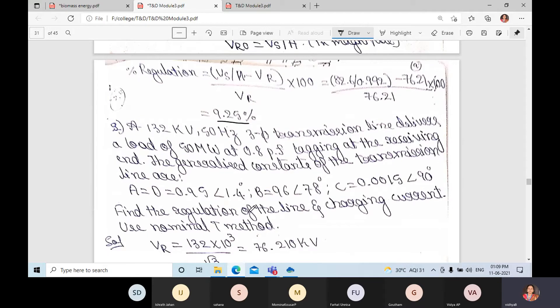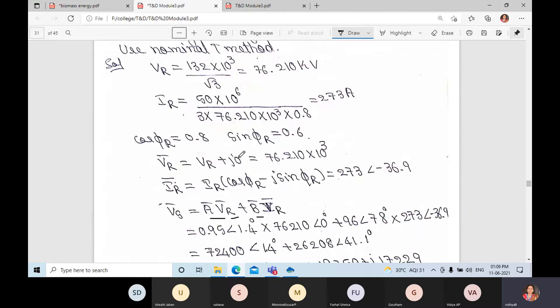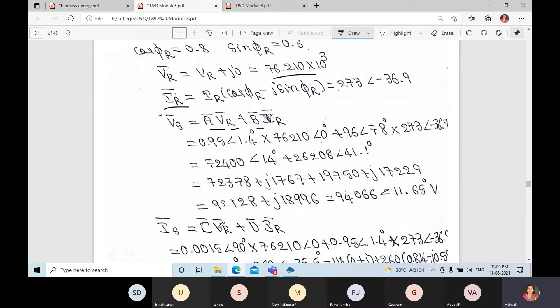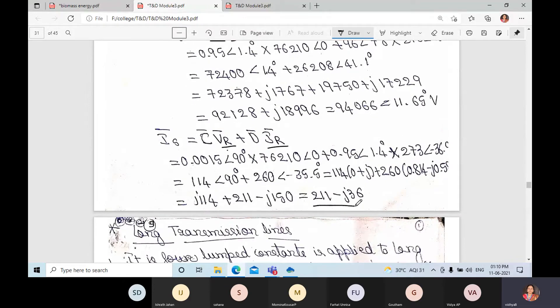For a similar problem, the ABCD constants — A, B, C, D values — are all given. We need to find Vs and Is. Compute Vr by dividing by √3, and Ir = P / (3 × Vr × cos φr). Calculate Ir vector and Vr vector similarly, then apply Vs = A·Vr + B·Ir and Is = C·Vr + D·Ir to get the answer: 211 − j36.